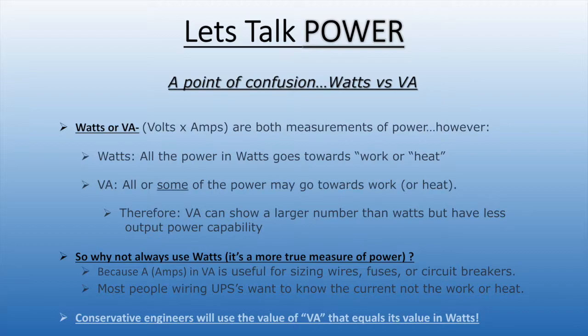So why not always use watts? It's a true measure of power, but amps in the VA figure are useful for sizing wires, fuses, and circuit breakers. Many people wiring UPSs want to know the current, not the work or heat. Conservative engineers will use the same value for VA as its equivalent in watts.